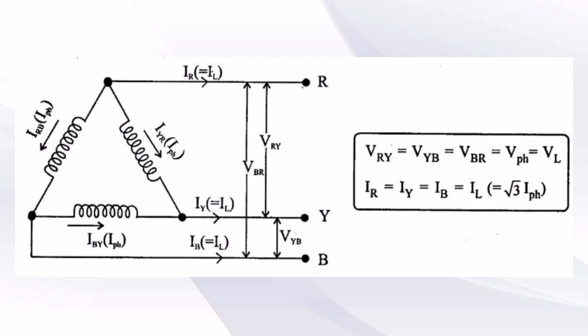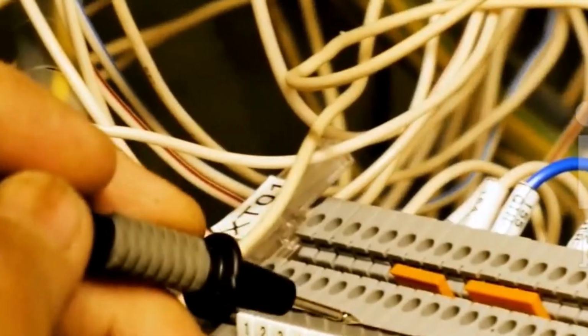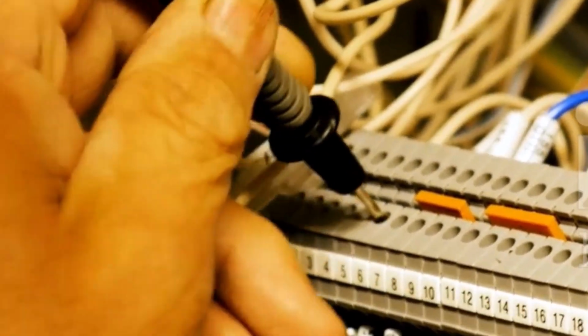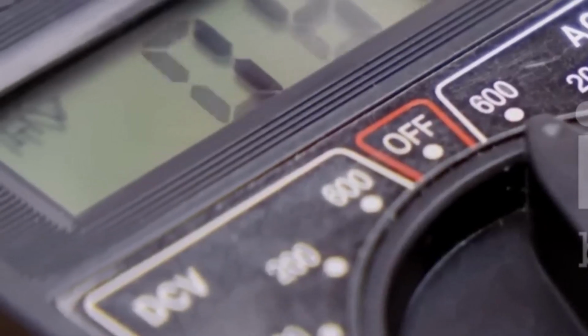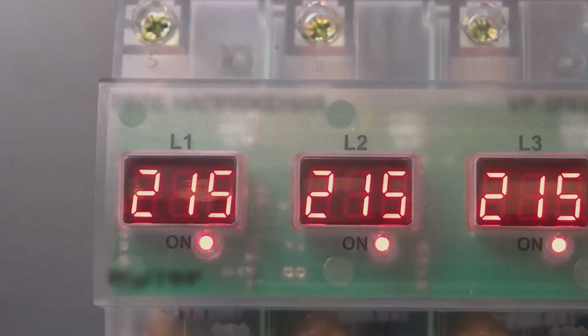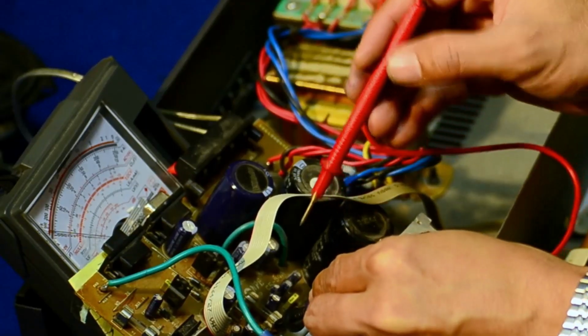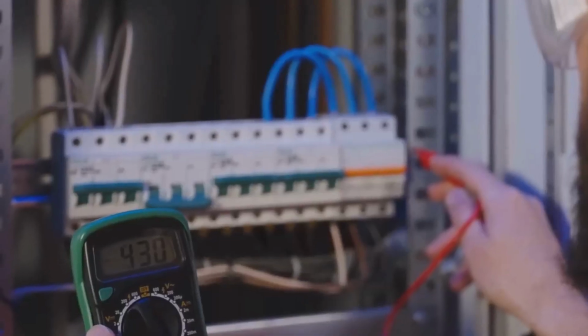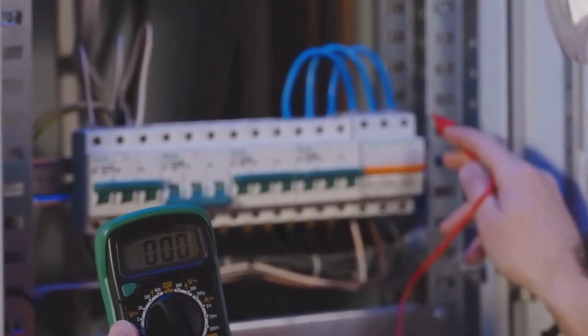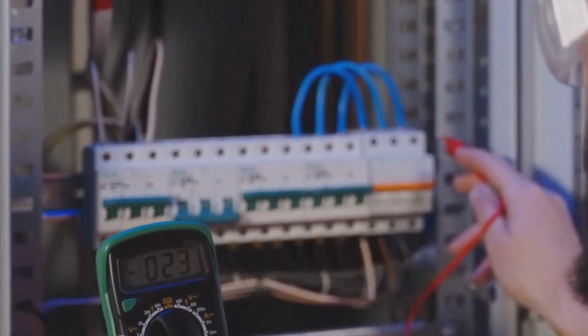Now that we know what a delta connection looks like, let's talk about the rules of electricity that apply to it. There are two main things we need to understand: voltage and current. Let's start with voltage. In a delta system, we have two types of voltage to consider: phase voltage and line voltage. Phase voltage is the voltage across a single phase winding, one side of our triangle. Line voltage is the voltage measured between any two of the main line conductors coming out of the junctions.